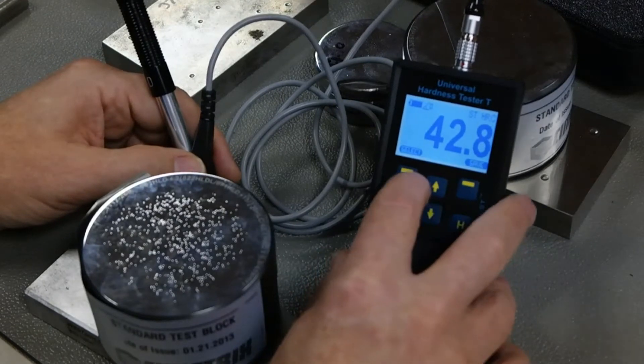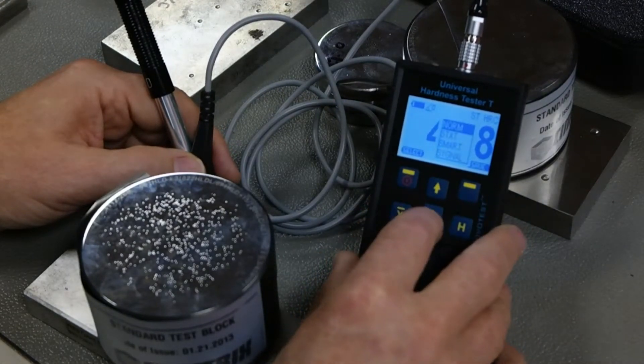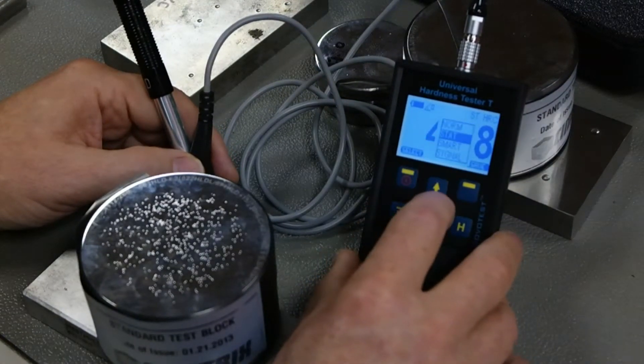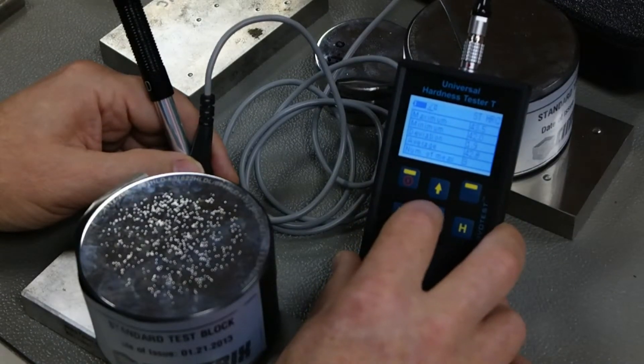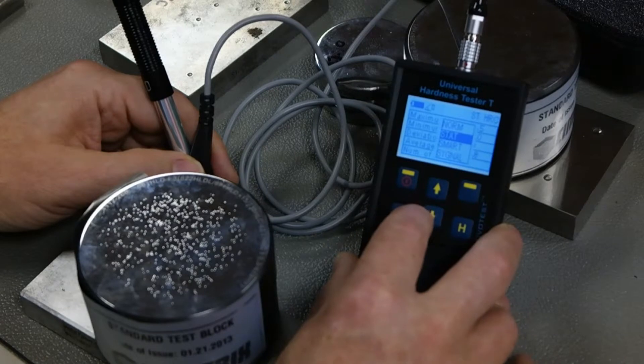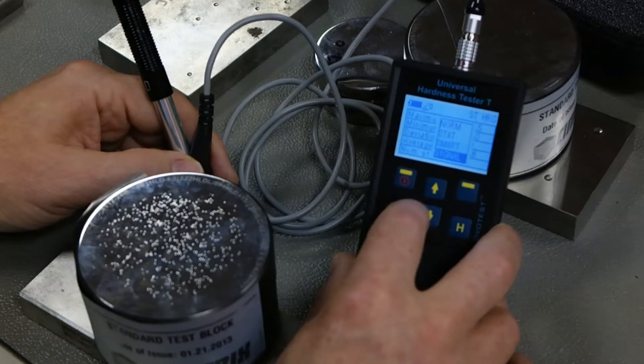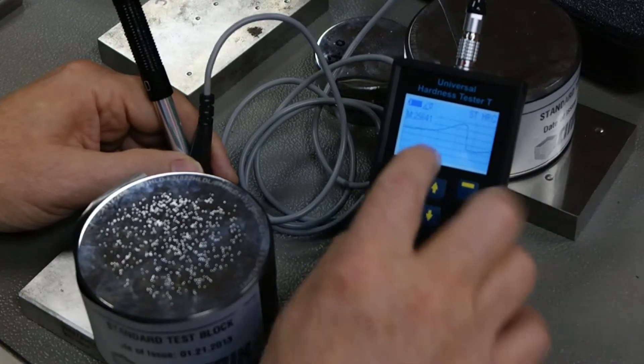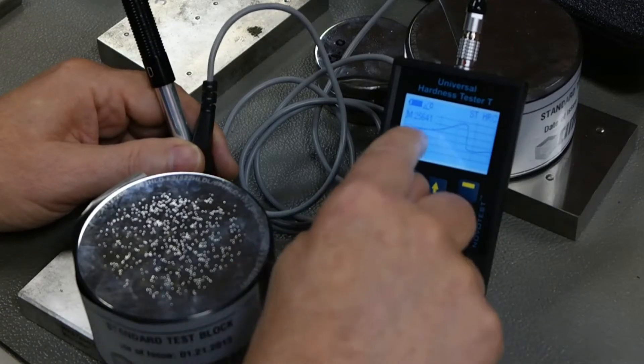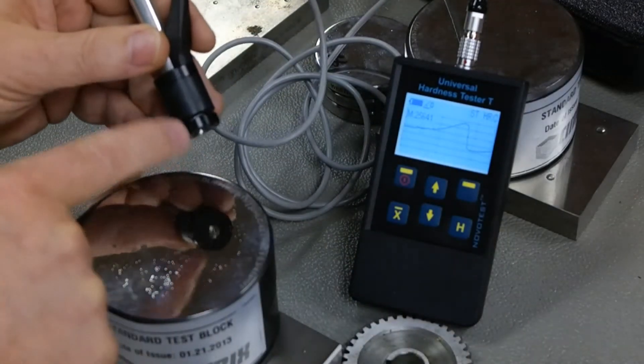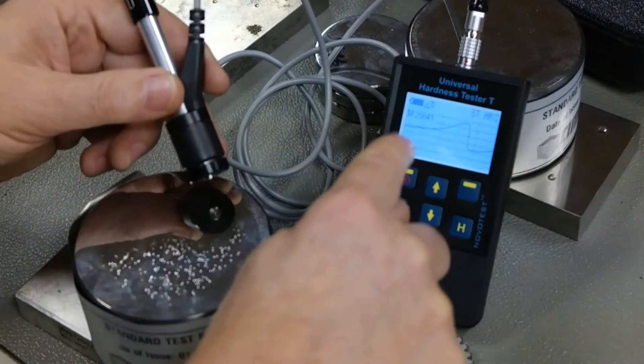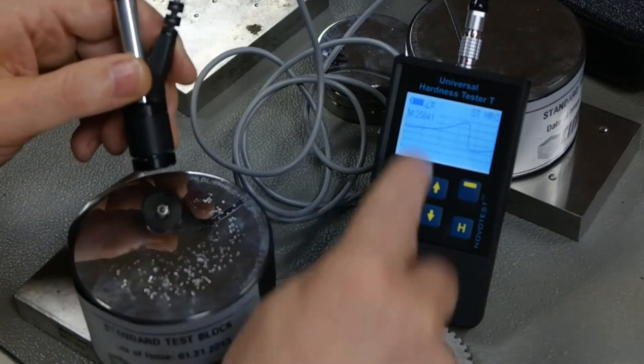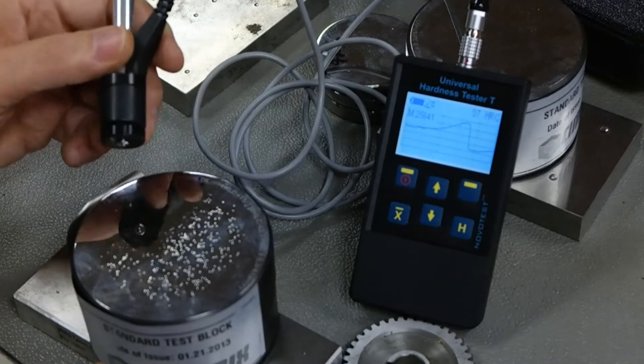The other nice little feature we have inside here for this is we still have the statistics and smart, but we also have signal. And signal shows the curve that is done from the acceleration past the coil of the impact body. And then the rebound rate going the other direction shows this in the display just for reference purposes.